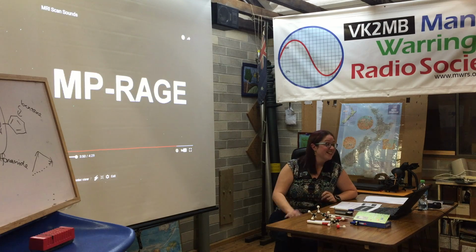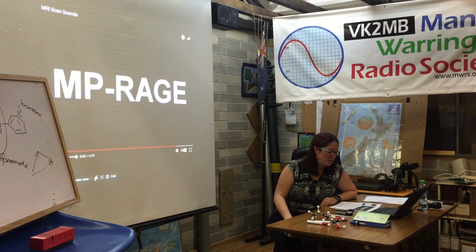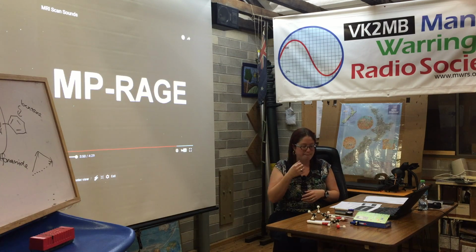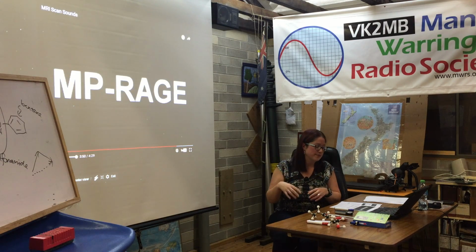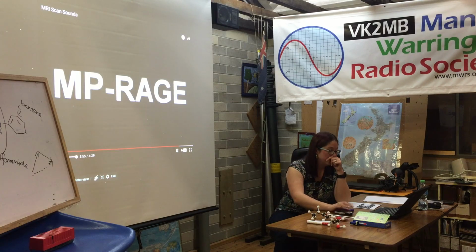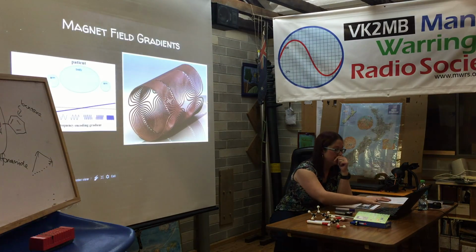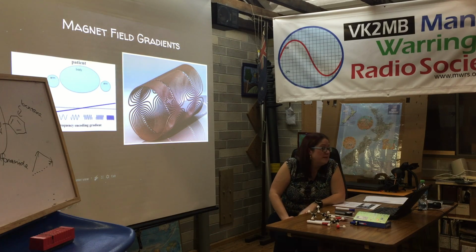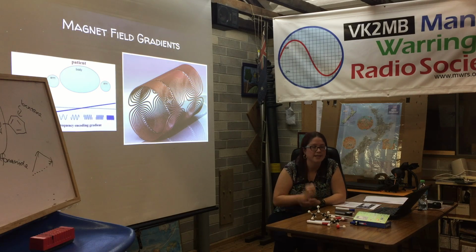The Russian machine. Yeah. So even as an operator, you have to have ear protection when you're doing this kind of work. It's deafening. The exact kind of sound that you hear is going to depend on the kind of sequence that they're actually running. But the origin of the noise is the fact that they are using gradients. I spent a lot of time talking about how homogeneity was vital and it had to be 1 part per billion and the same everywhere.